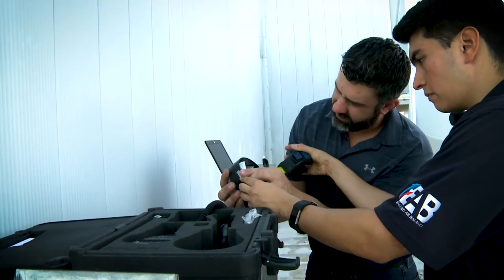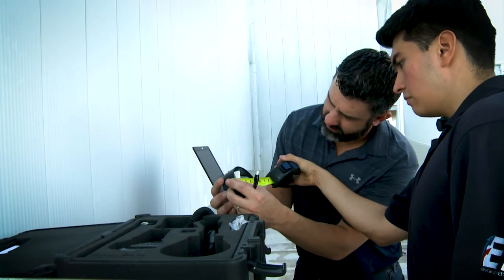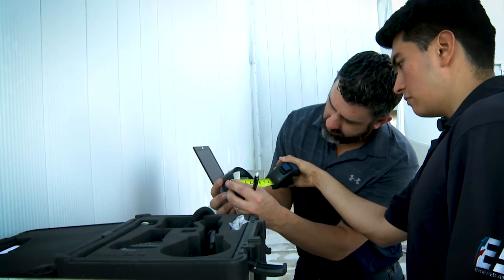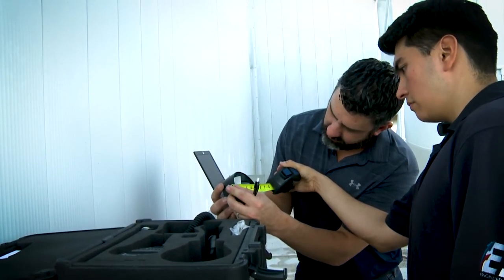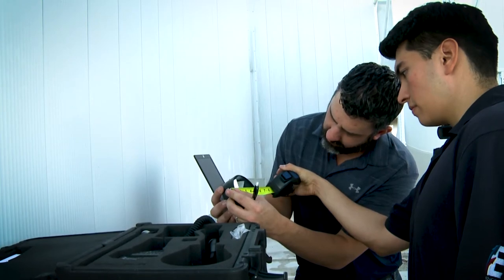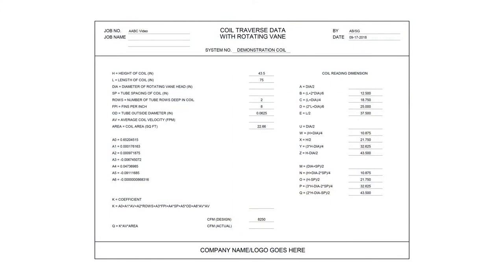The AHU-1 submittal data did not include the diameter of the rotating vane head. The DIA measurement was taken while in the field by measuring the inside diameter of the rotating vane anemometer's head as four inches. Record the measurement in the coil traverse data with rotating vane form: DIA equals diameter of rotating vane head as four inches.